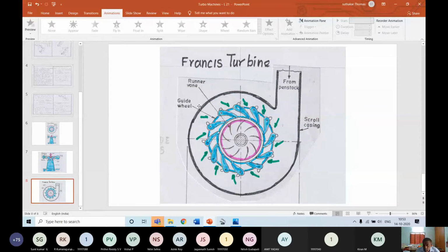So mostly by controlling some valve. So there must be an automatic control system where the speed of the turbine will be sensed. It will be compared with the required speed, and a signal will be sent proportional to the difference to actuate the valves. It will be a continuous process like this, the speed governing.